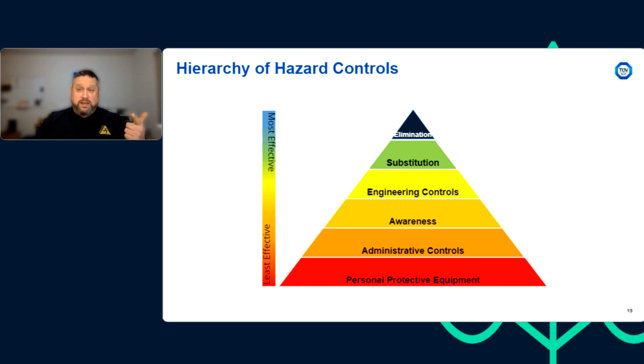So now we have to apply lockout, tag out, which is sometimes new for us in this industry. And then we have to verify that it's de-energized. Here in North America, that means we're getting a meter, we're going to check it on a live circuit to make sure it's working properly, verify our de-energized circuit is de-energized, and then check that meter on a live circuit again to make sure it's still working properly before we can say for sure that system is safe for us to touch without PPE.